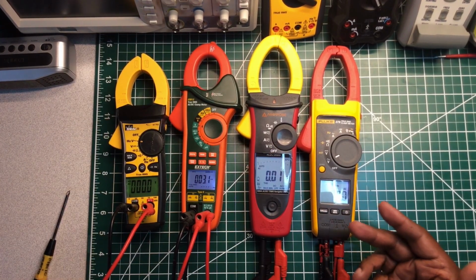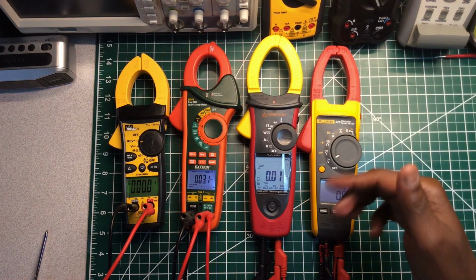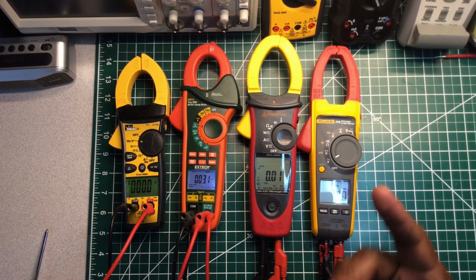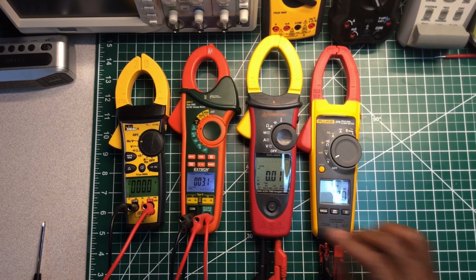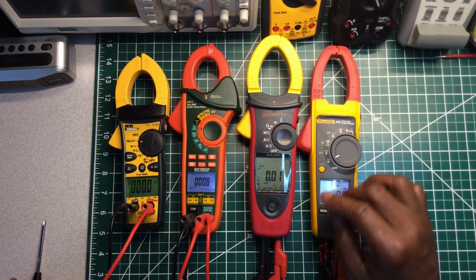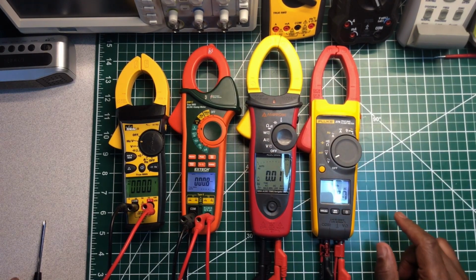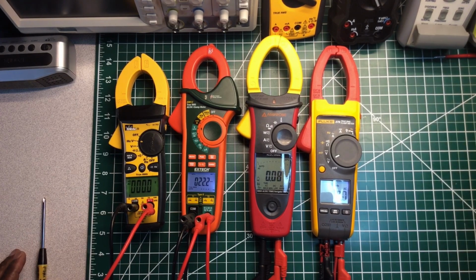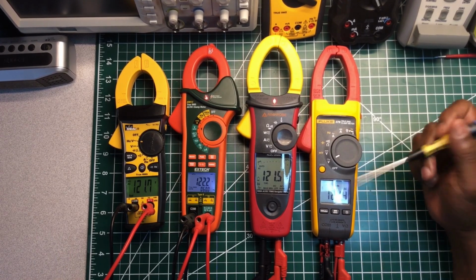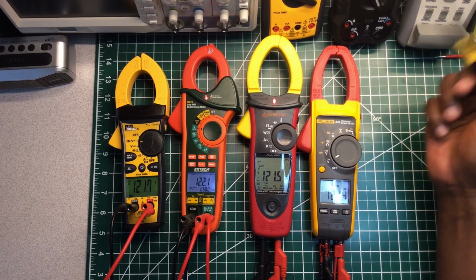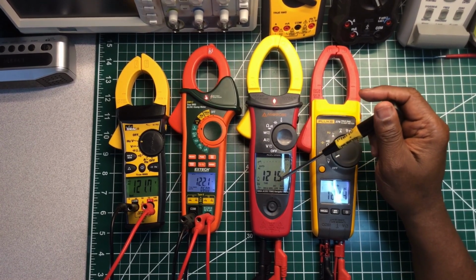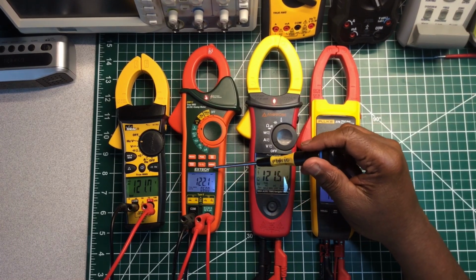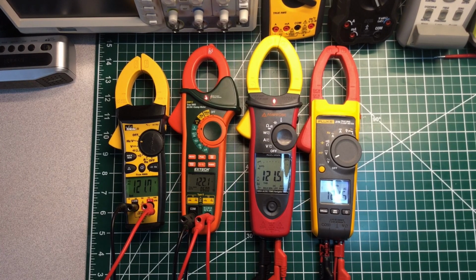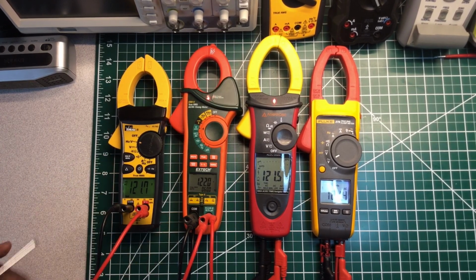Now, I have the meters connected in series to a power outlet here on my electronic bench, and I'm gonna turn it on, and I want you to see the readings that all of them give you on a 120 volt system. Okay, so make sure it's on AC. So here we go. Just take a sample reading. All right. The Fluke is giving me 121.4 volts AC. The Amp Probe is giving me 121.5 AC. The Extech is giving me 122.1 AC. And the Ideal is giving me 121.7.